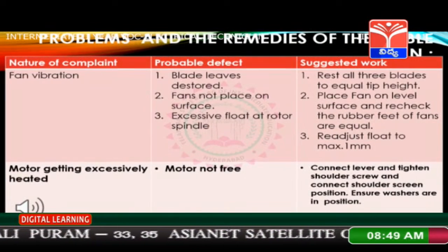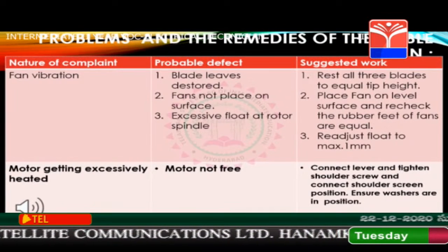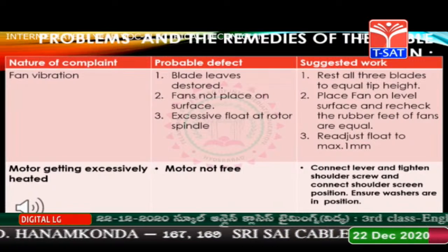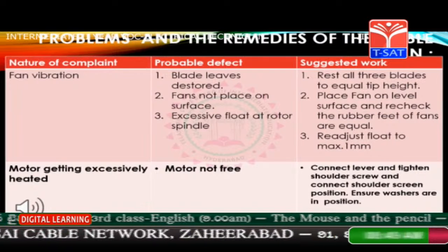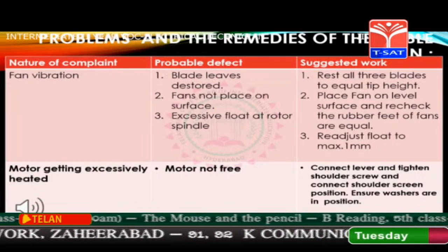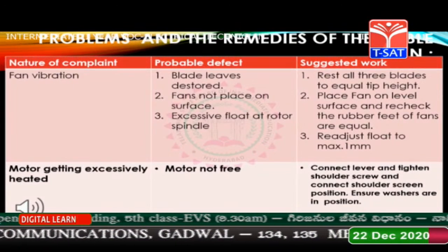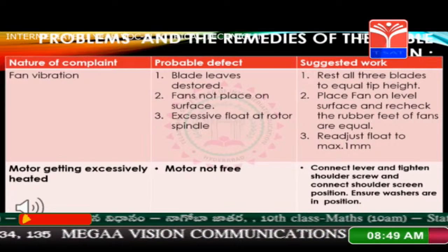1. The reason: blade leaves distorted. Suggested work: reset all 3 blades to equal tip height. This is rectified. The defect in most cases is that blades are dynamically balanced at the factory.